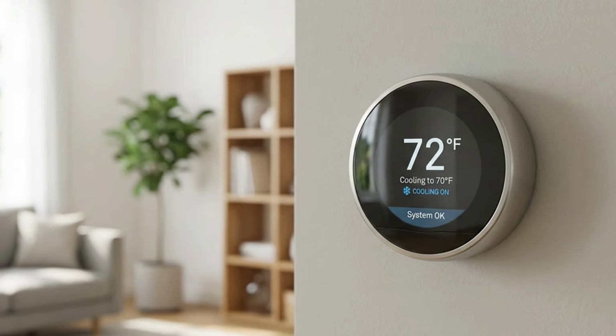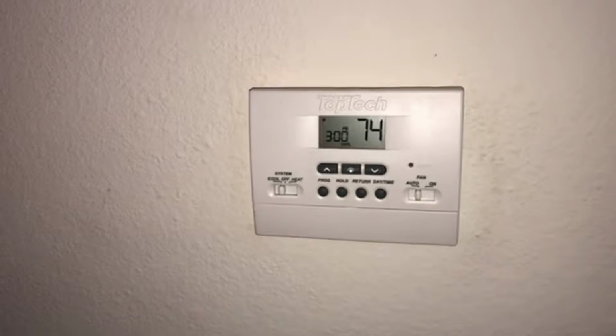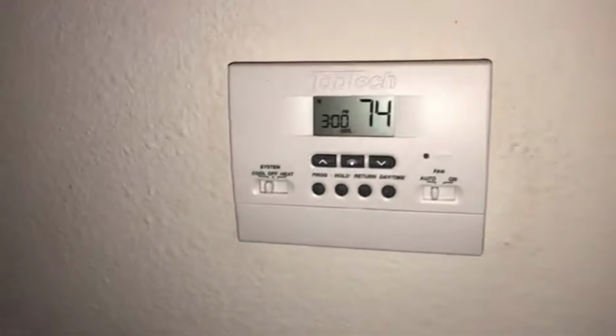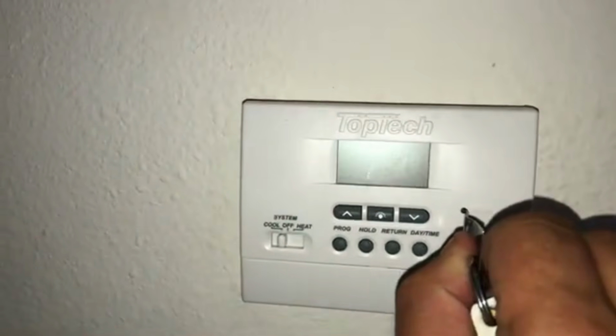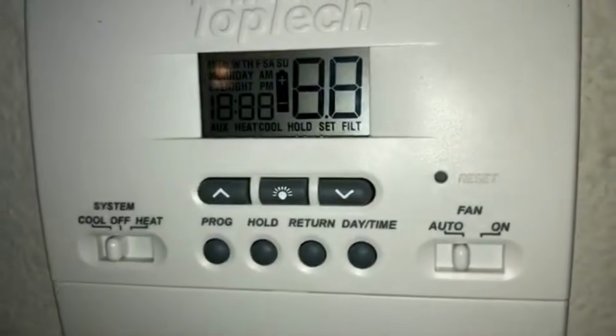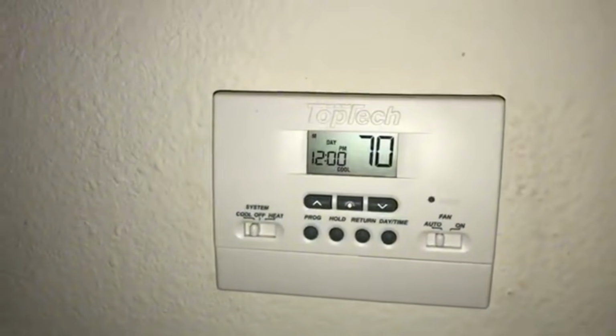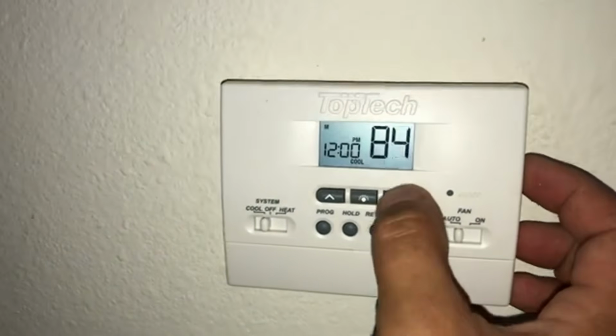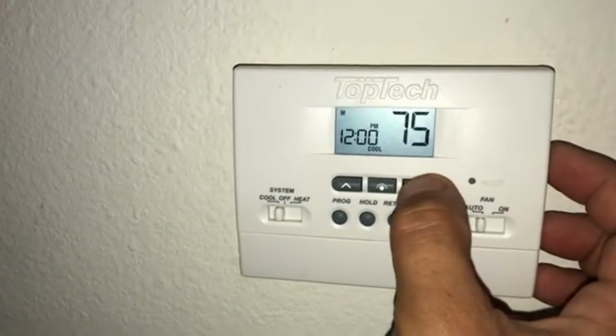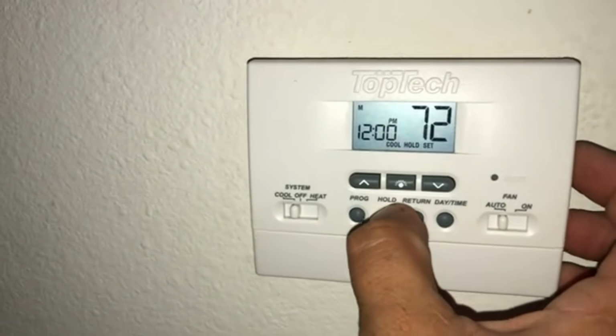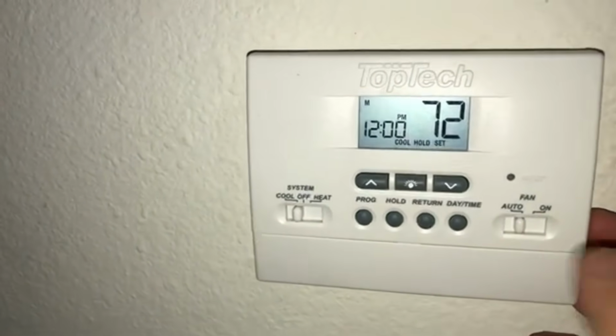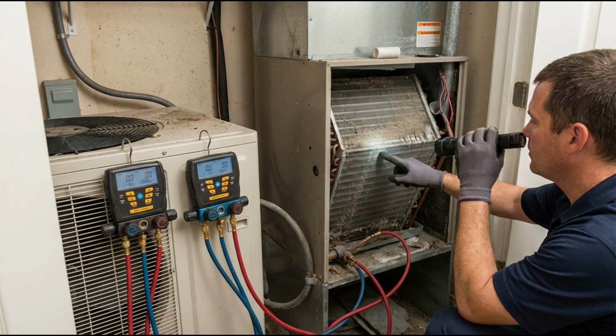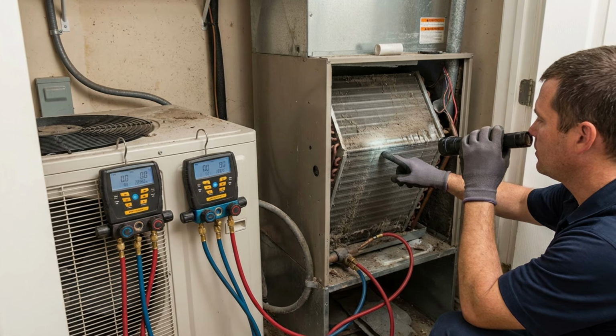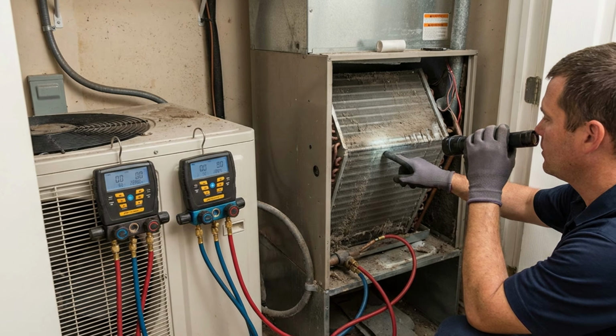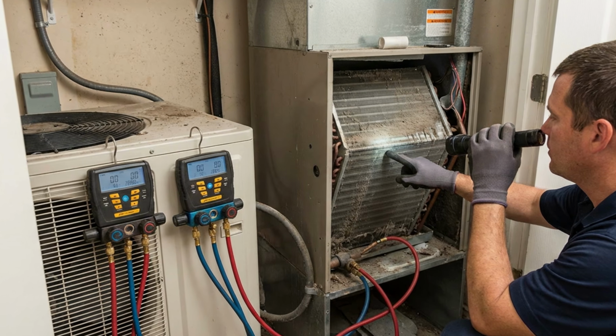That's the maintenance window that extends compressor life by years. Mistake 4. Ignoring what your thermostat is actually telling you. Your thermostat is more than a temperature dial. It's a diagnostic tool, if you know how to read it. Pay attention to how long your system runs to satisfy a call for cooling or heat. If it's short cycling, running for 5 or 10 minutes, shutting off, then starting again 20 minutes later, something is wrong. That could be an oversized system, a refrigerant issue, a dirty coil, or a failing component.